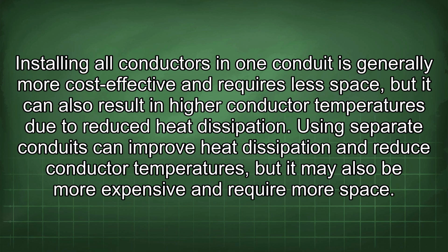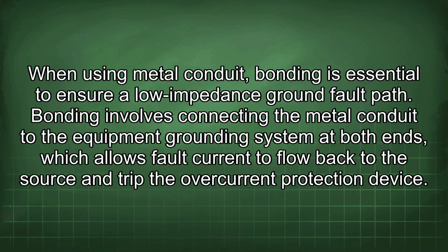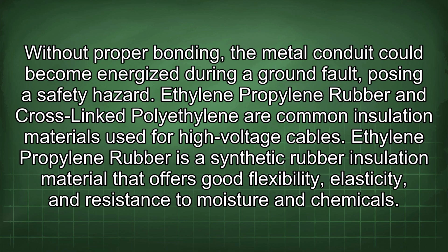When using metal conduit, bonding is essential to ensure a low impedance ground fault path. Bonding involves connecting the metal conduit to the equipment grounding system at both ends, which allows fault current to flow back to the source and trip the overcurrent protection device. Without proper bonding, the metal conduit could become energized during a ground fault, posing a safety hazard.